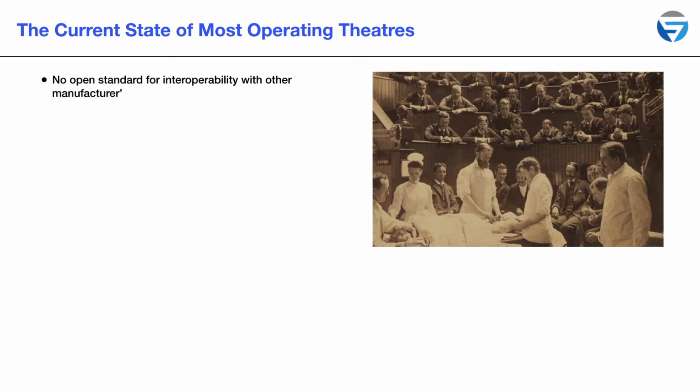There is no open standard for interoperability with other manufacturer systems. So the major endoscopic companies or the lighting companies or the table companies, they have their own protocol to control their devices, and you can't mix and match. Only 5% of endoscopy imaging systems in the UK are actually connected to the network at all. They're just frame grabbers, effectively.